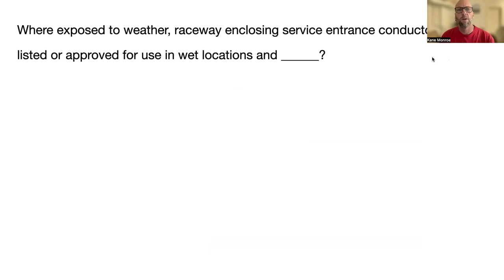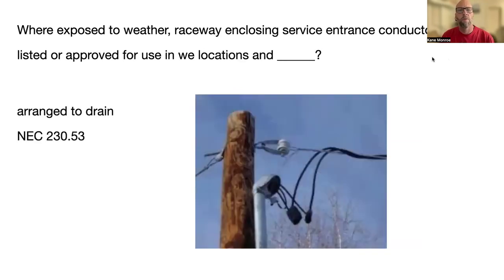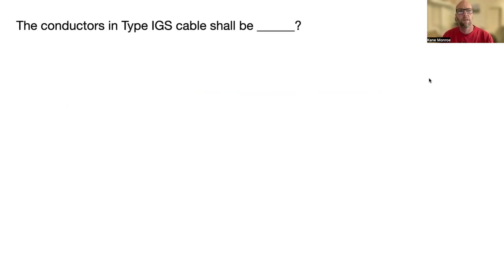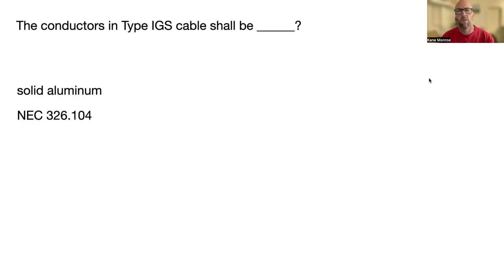In this picture you'll see how, down in the connection area, they're allowed to drain out — they don't drain into the conduit. That's NEC 230.53. The conductors in Type IGS cable shall be solid aluminum — that's NEC 326.104.